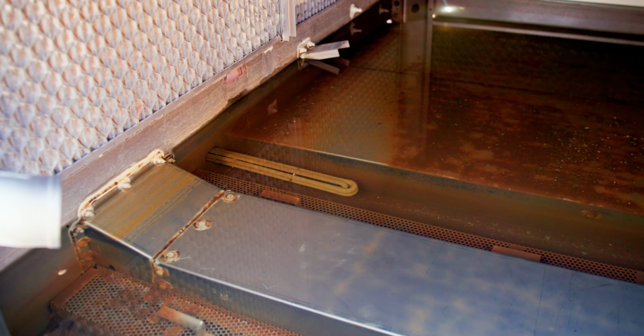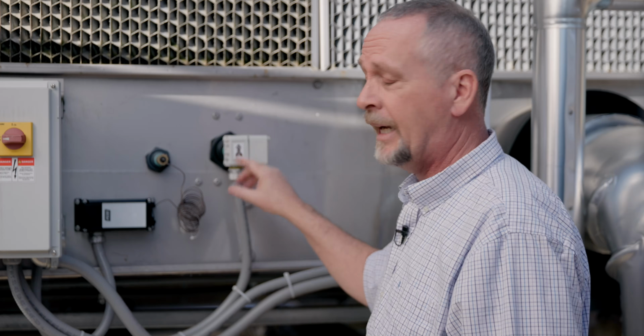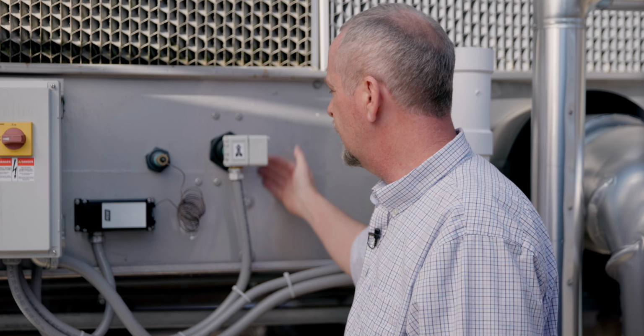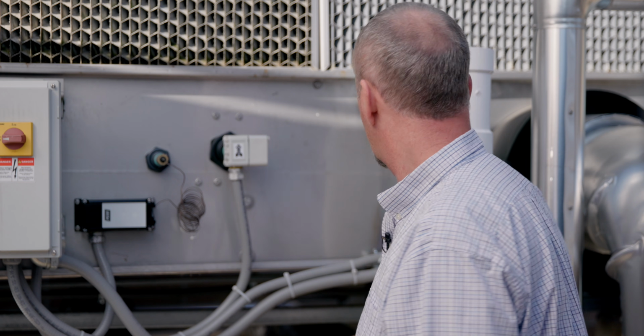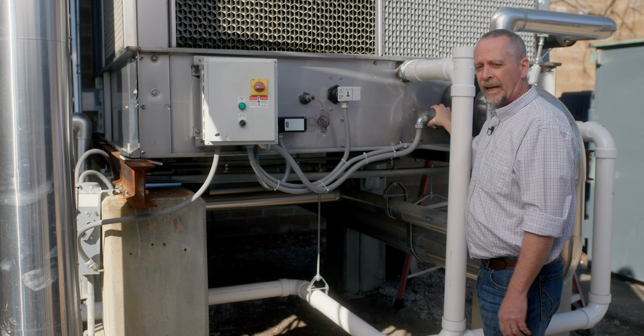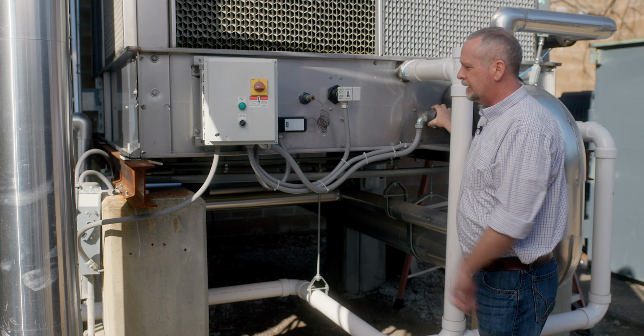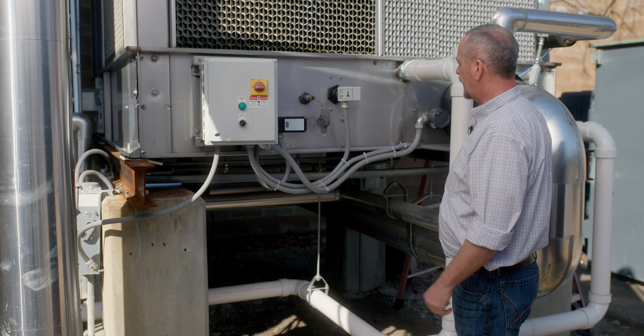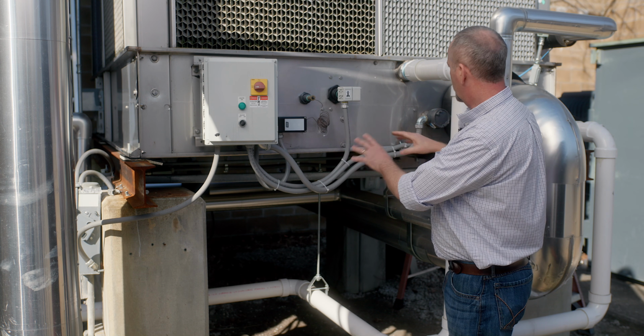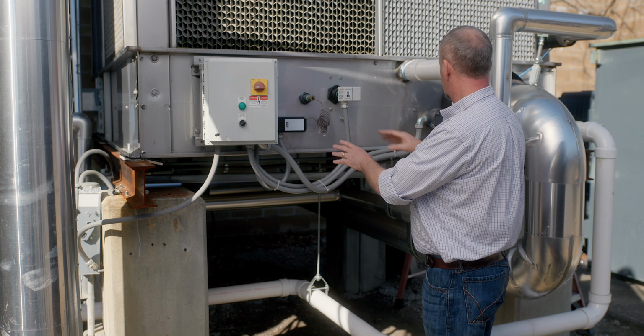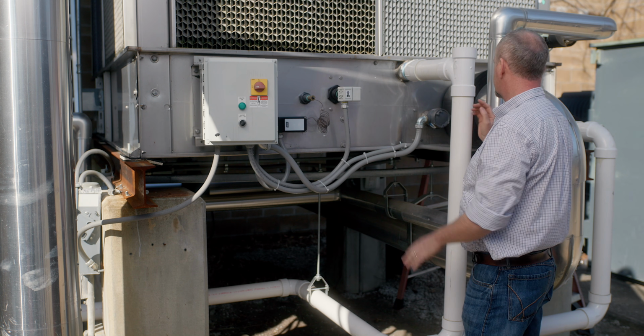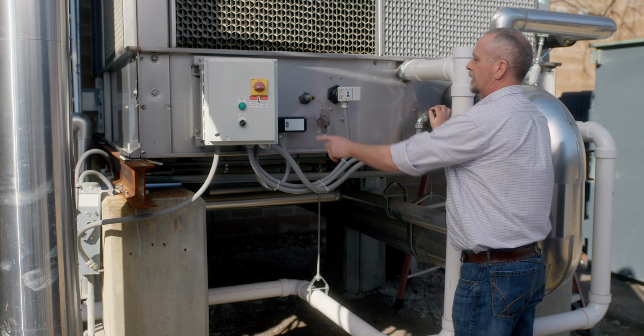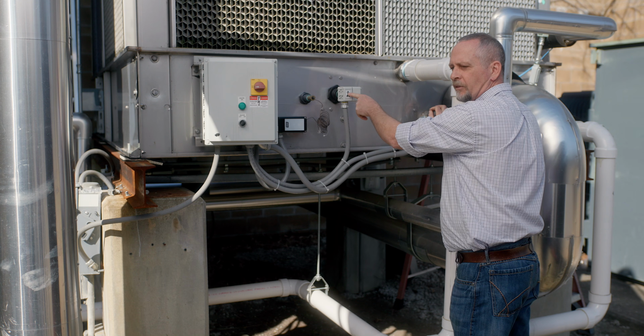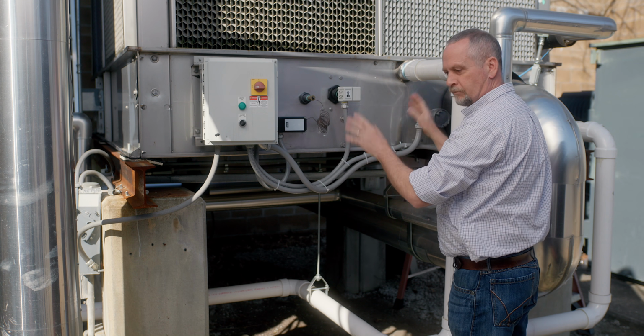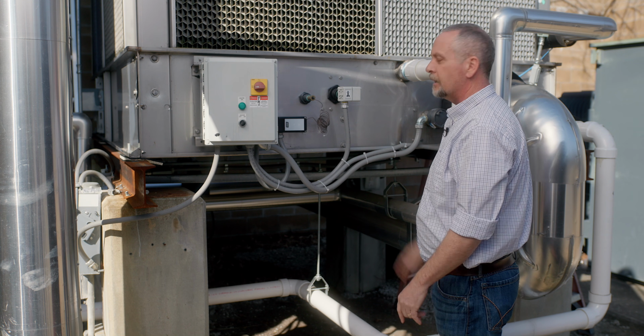So if this switch were defective, or somebody had jumped it out, or it's not installed and working properly, you've got the potential of your tower being almost out of water, banging on this electric heater, and then you smoke your heater, and then you're in bad shape here. So the three components involved in heating the basin water inside that tower are the heater, the thermostat, and then my safety float switch that lets me know my tower's got water in it, I'm okay to turn this heater on.